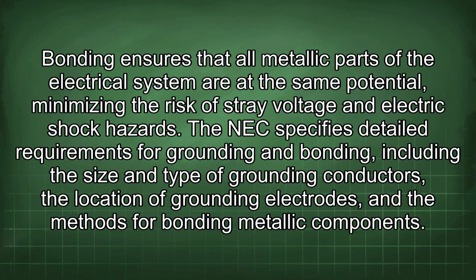Bonding ensures that all metallic parts of the electrical system are at the same potential, minimizing the risk of stray voltage and electric shock hazards. The NEC specifies detailed requirements for grounding and bonding, including the size and type of grounding conductors, the location of grounding electrodes, and the methods for bonding metallic components.